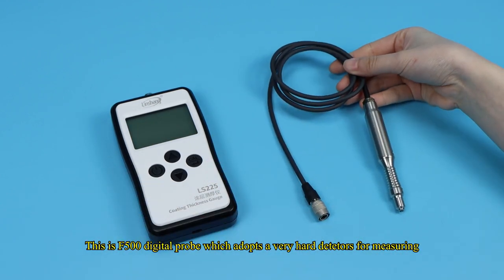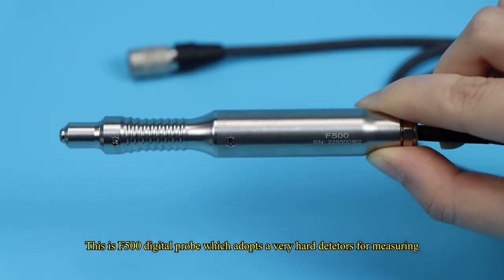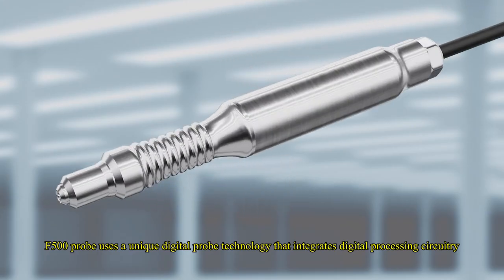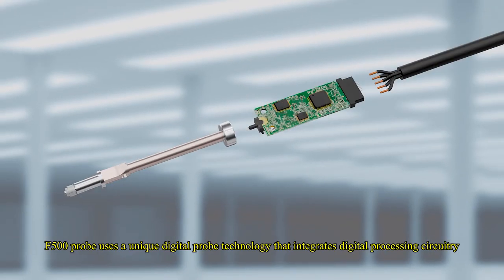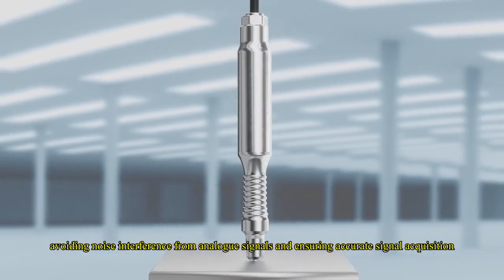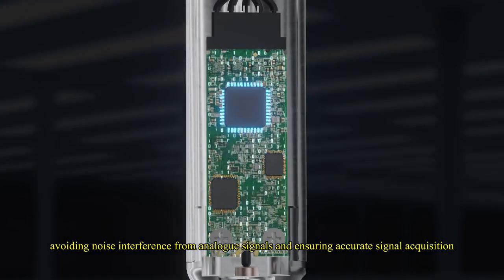This is F-500 digital probe which adopts a very hard detector for measuring. F-500 probe uses a unique digital probe technology that integrates digital processing circuitry, avoiding noise interference from analog signals and ensuring accurate signal acquisition.